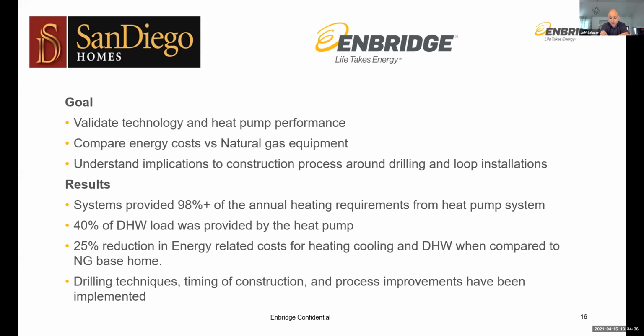The results were exceptional. The systems provided 98% or greater of the annual heating requirements, needing electric backup only a small percentage of the year, and they were sized to approximately 80% of that peak heating load. So sizing of the heat pump is critical on these systems, and we've recognized that.